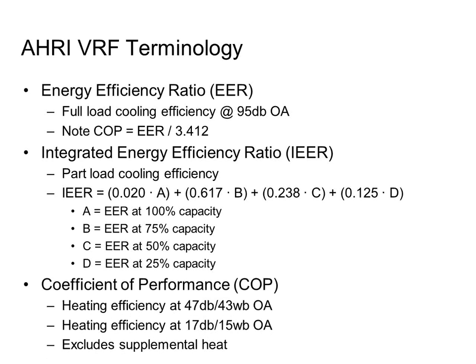You'll also notice that there's COPs on there for the heating mode. The heating mode is tested at 47 degrees outside and 17 degrees outside. The 17 degree number in almost all cases is going to be less than the 47. There are some units that have a quirky scenario where it could actually be higher, but that's a whole other debate and an irregularity. So usually as the temperature drops outside, so does the efficiency and the capacity at those levels.